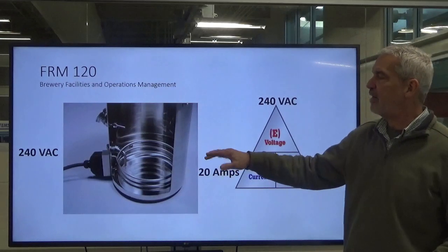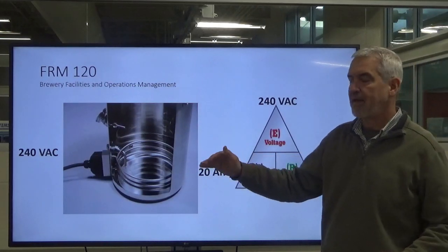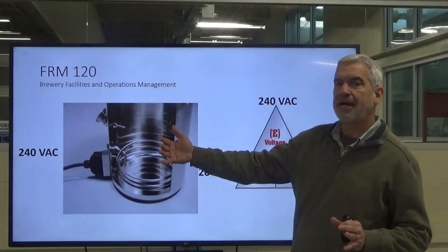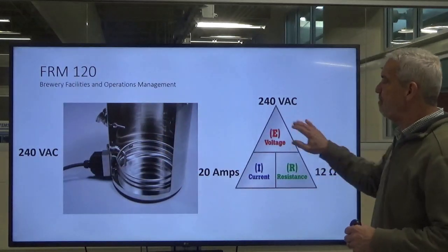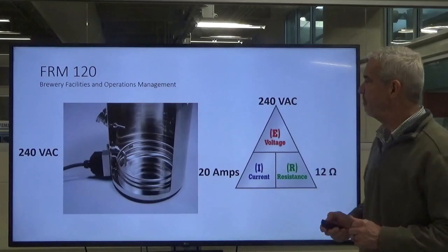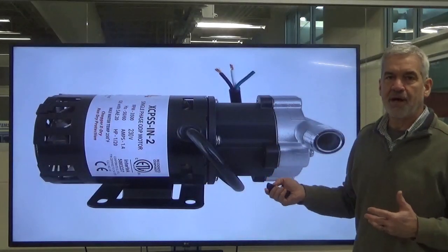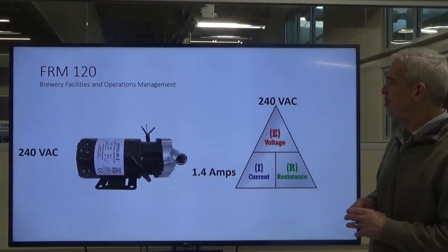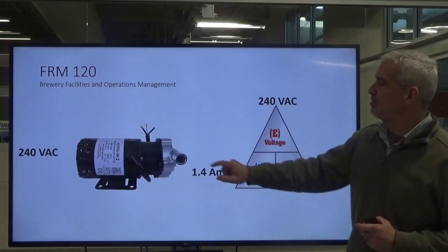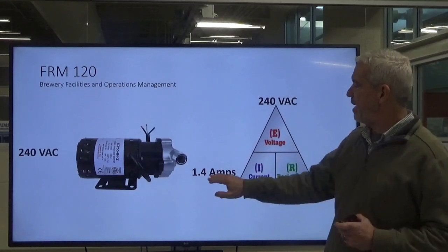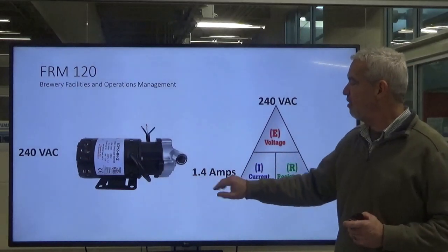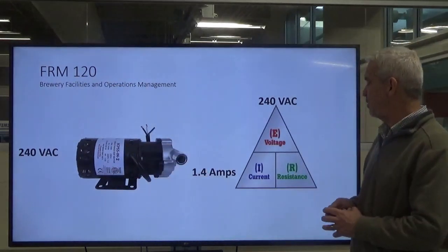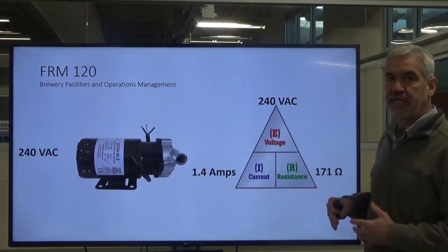The heat will make that vary a little bit because heat impacts resistance, so it could vary. But mathematically, this is what it should be. And of course, we use pumps for transferring our liquids. In this example, if we have 240 volts applied to our pump and it pulls 1.4 amps, we can expect the windings in this motor to have a resistance value of about 171 ohms.